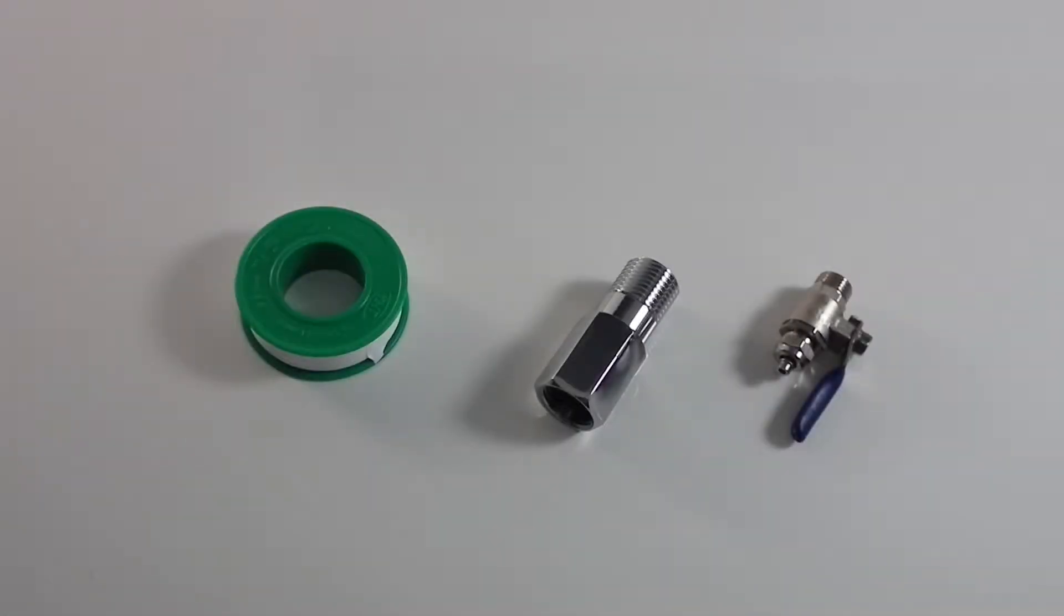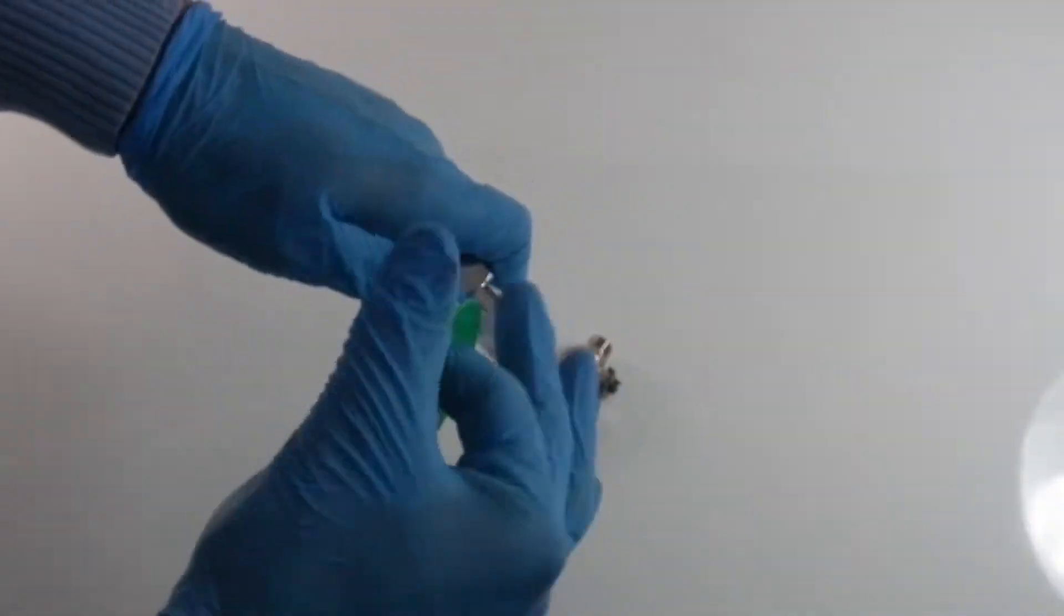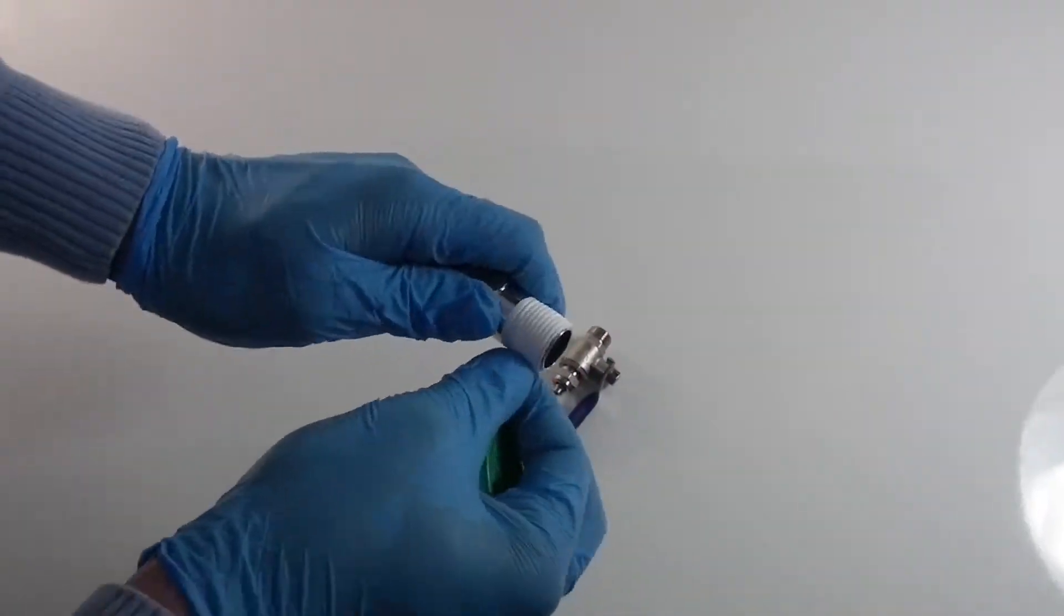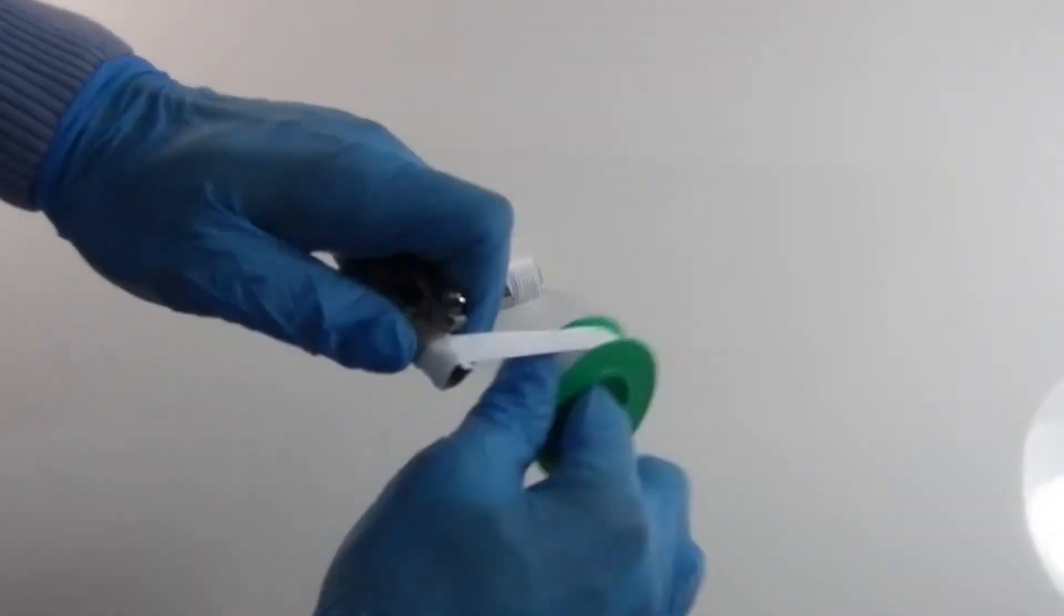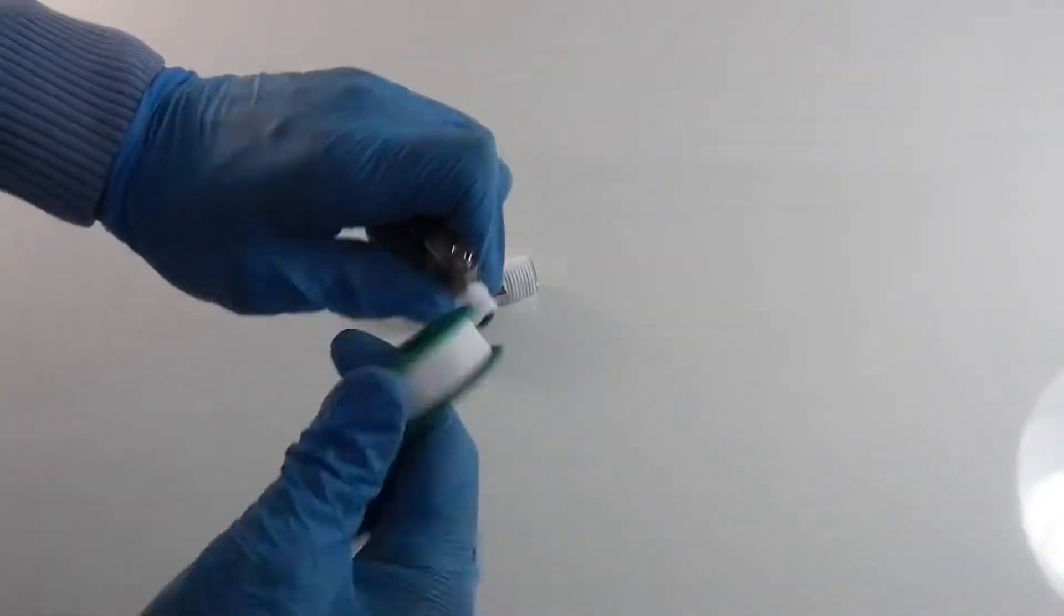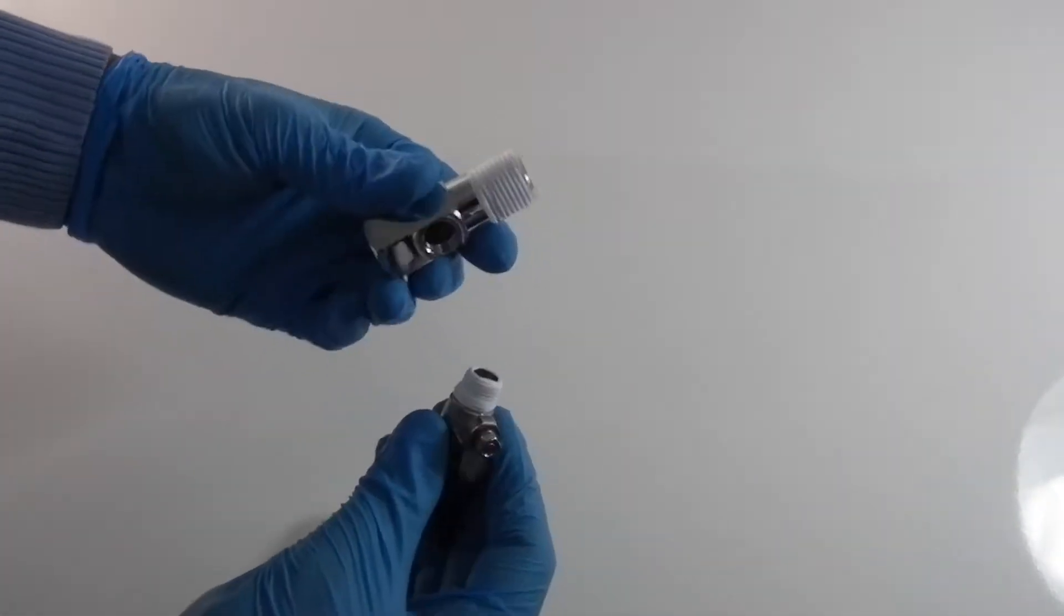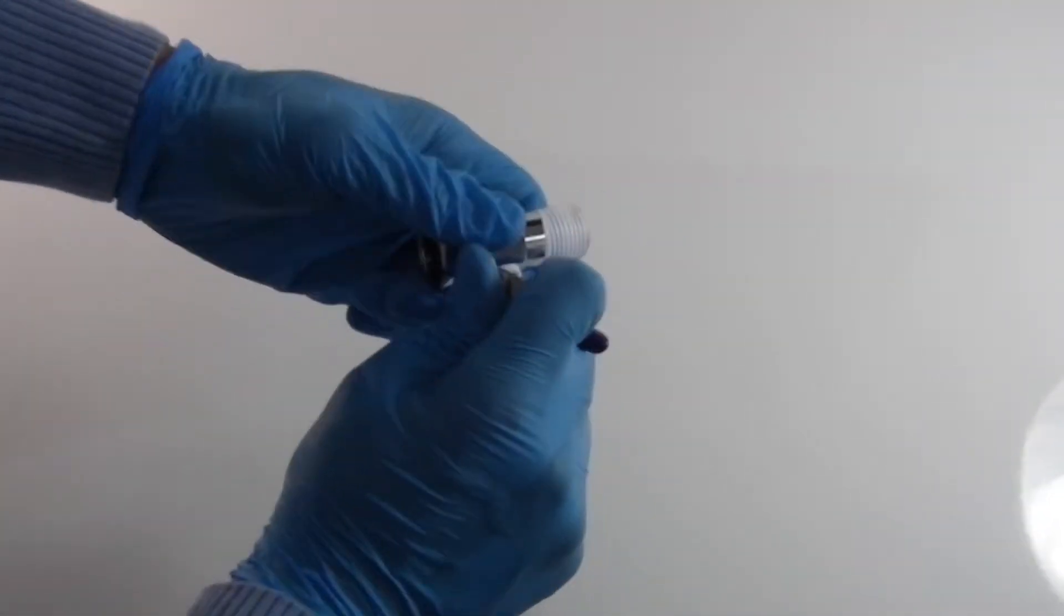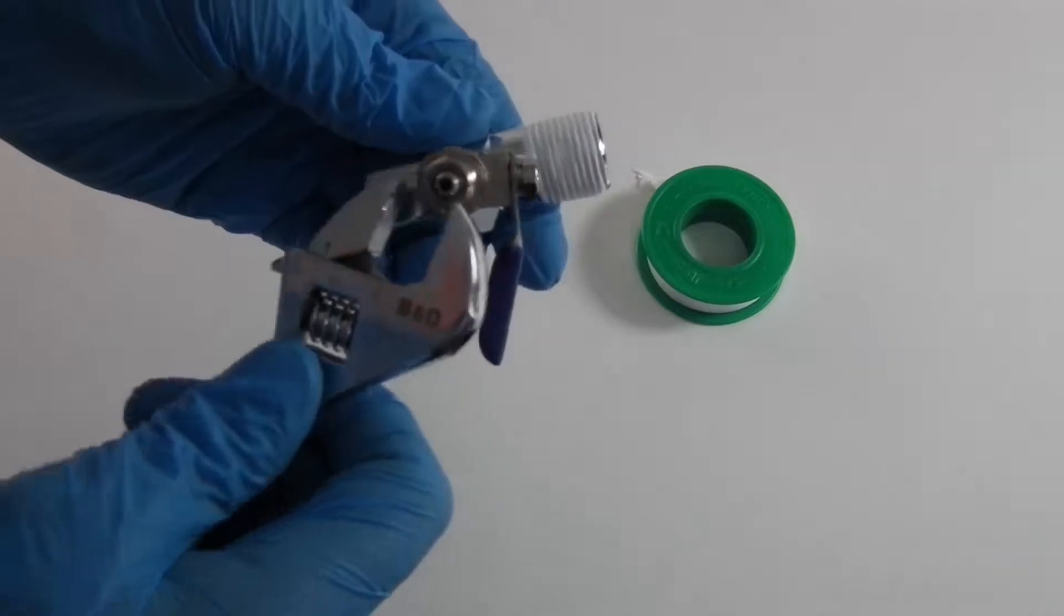For the next step, let's assemble the feed water system. Be sure you have the diverter valve, the metal ball valve, and PTFE tape. Apply PTFE tape around the diverter valve male thread connection side and the same for the metal ball valve. Then screw the ball valve into the diverter valve and make a full tightening with a spanner.